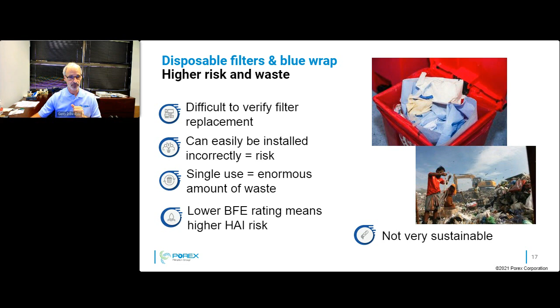So, switching to a reusable sterilization filter, these products are designed and can last the entire life of the device. There's products that have been tested up to 5,000 cycles. So typically, sterilization containers used several thousand times, it can last the entire life. The material can be repurposed at the end of life. The PTFE filters can be reprocessed.